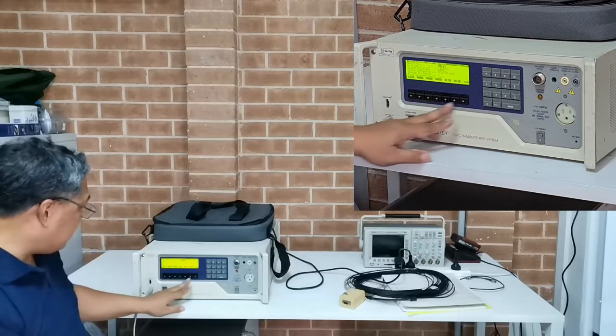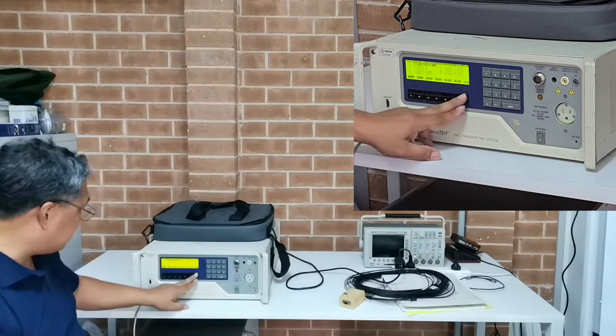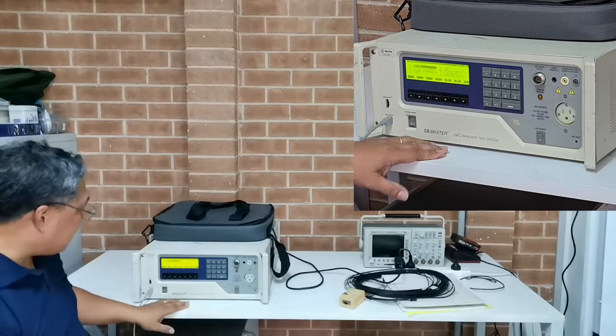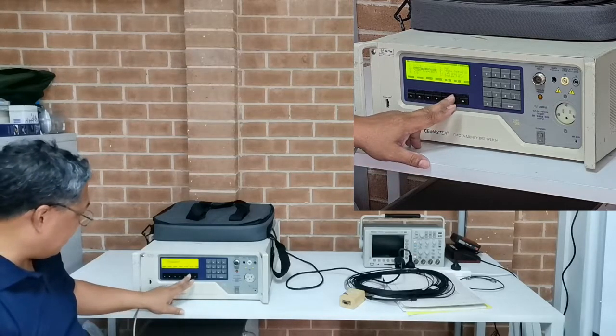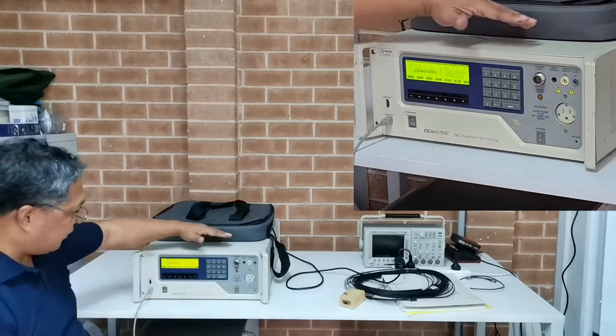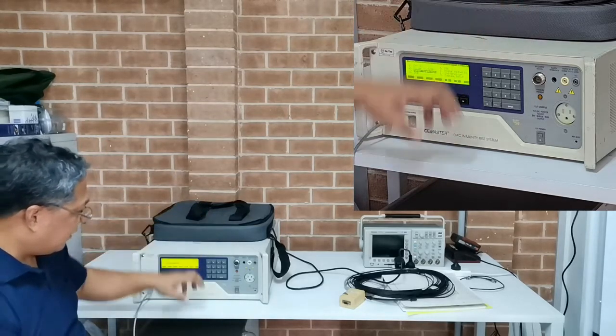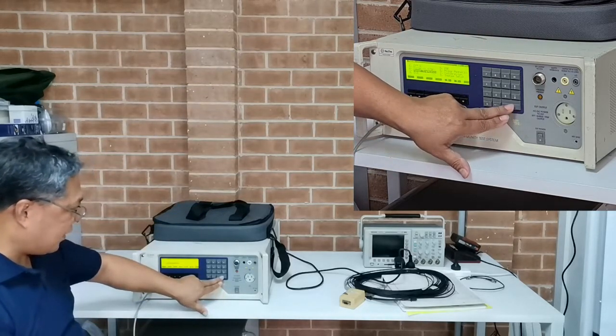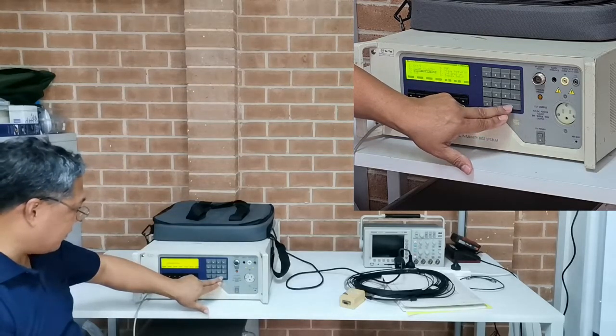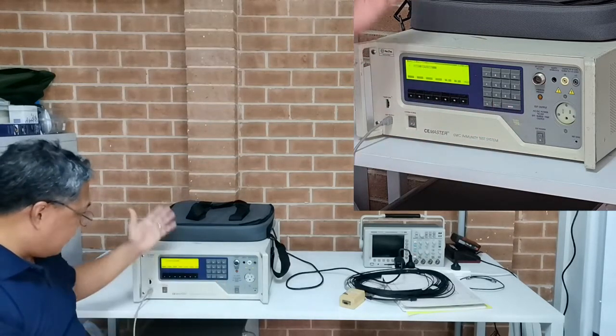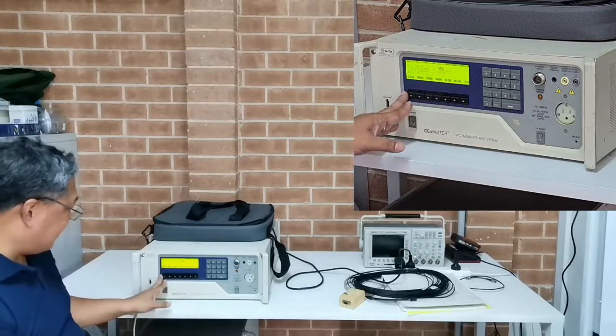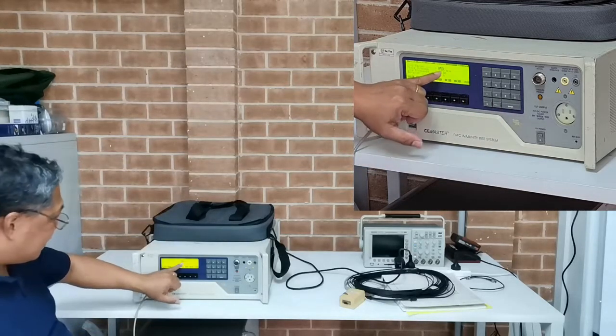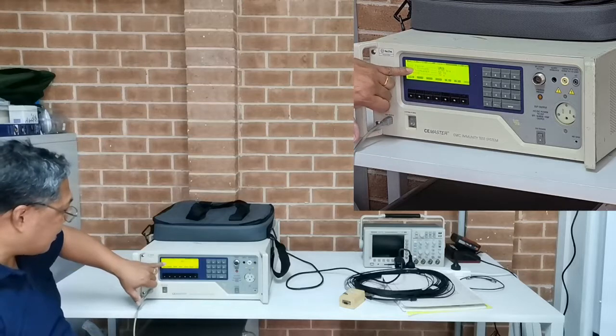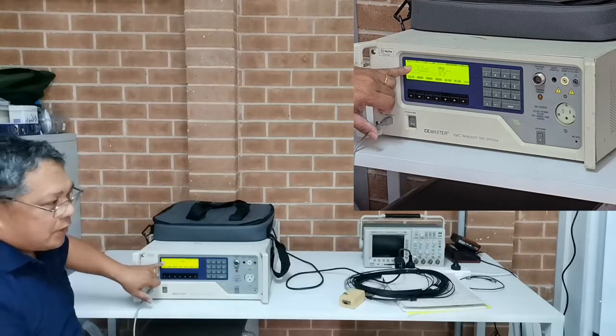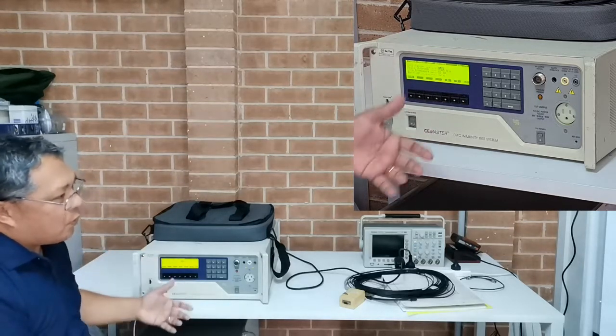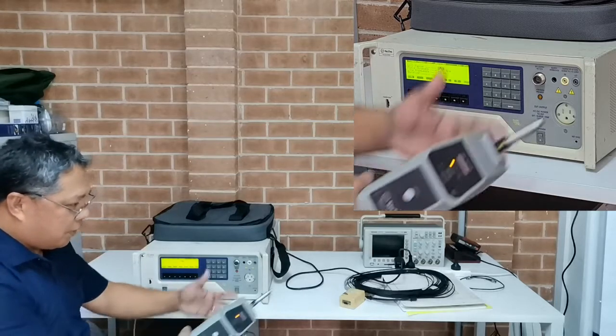So the next one we can try is power frequency magnetic field. We don't have the loop at the moment, but we'll see if this one has an option. It's a magnetic field option, which is a bonus. It's really a good thing. So it says user defined. It's great. It says 0.87. The first on the top is the coil factor. This is where you set the coil factor. You need to know the coil factor of your loop.